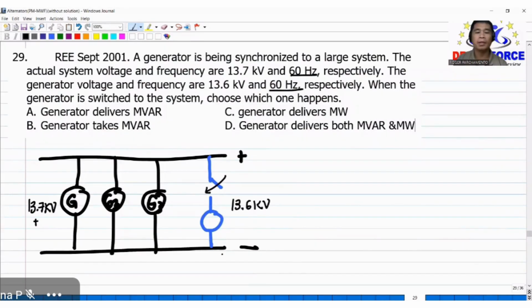So that upon switching this, the connecting switch, so ang tendency kasi ito, pag V no load tapos V full load, bababa siya, no? Dito yung V system voltage terminal, bababa siya because that is the characteristics of a generator. As the generator is being loaded, the terminal voltage goes down from the no load voltage or the generated voltage. So in this case, instead na mag-supply siya ng power, magdo-draw ngayon siya. Okay? It will draw power.